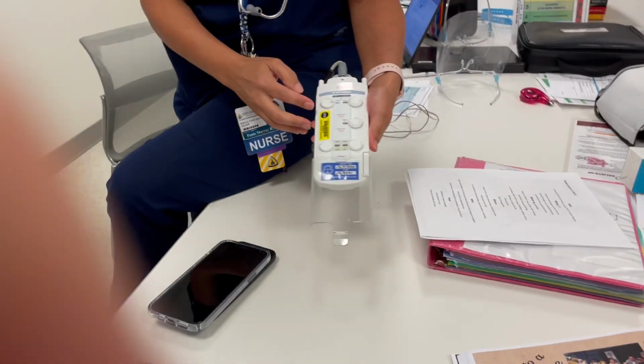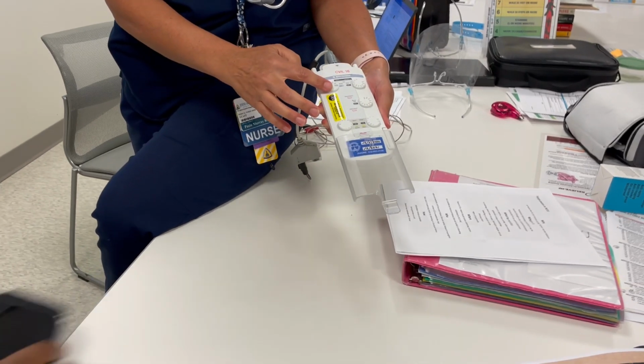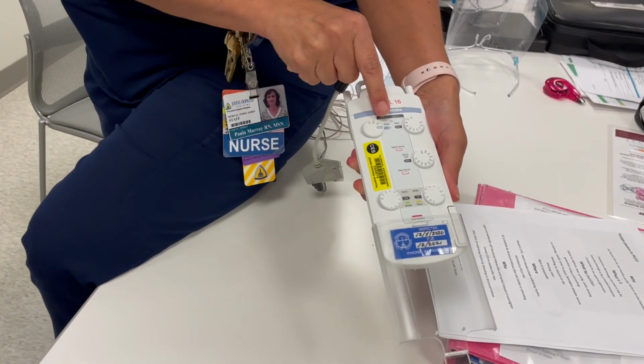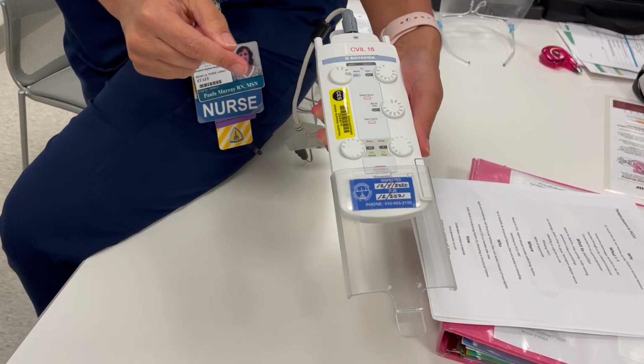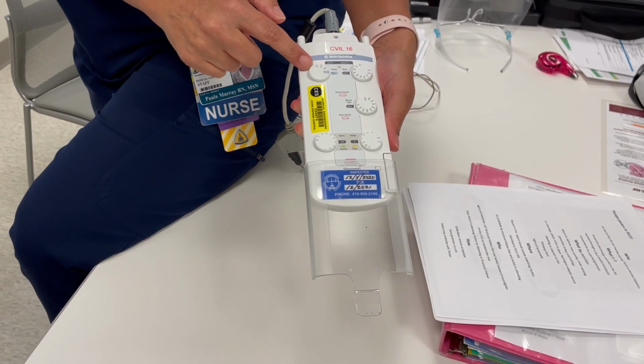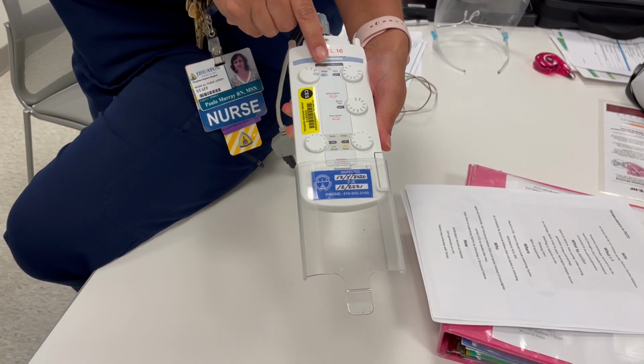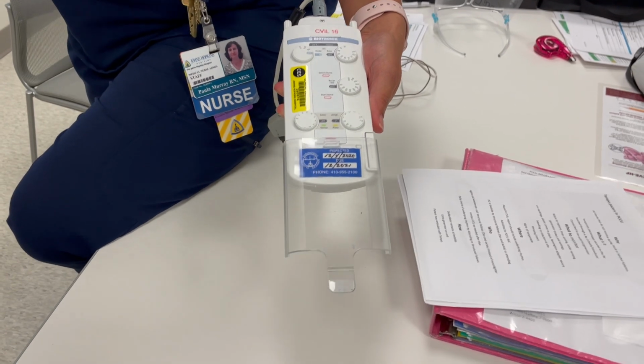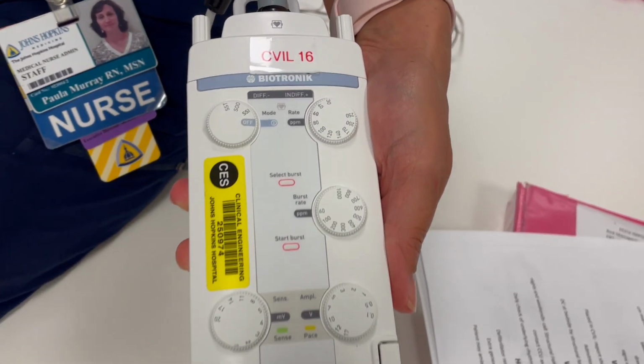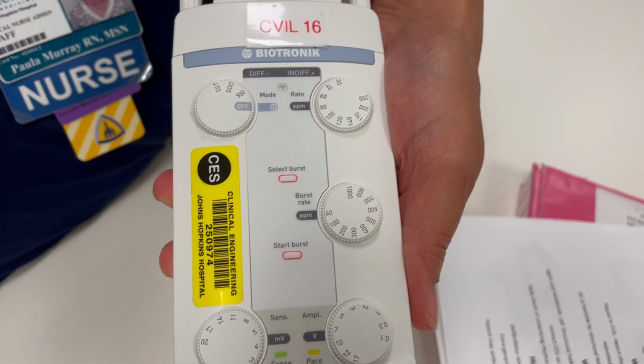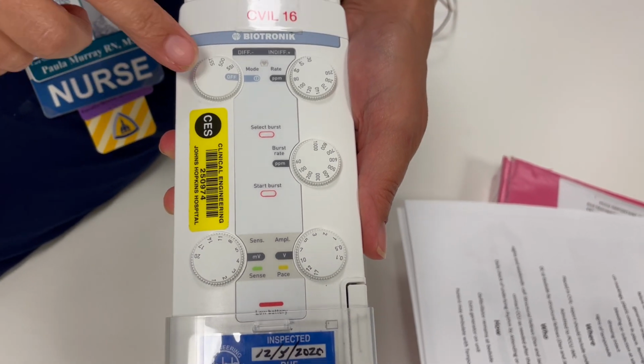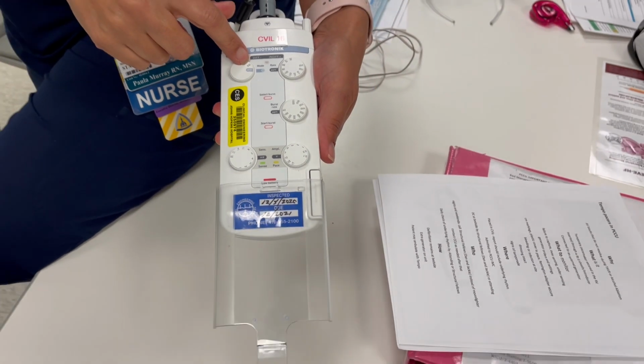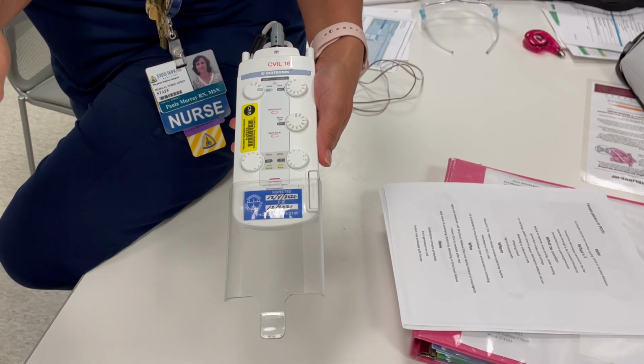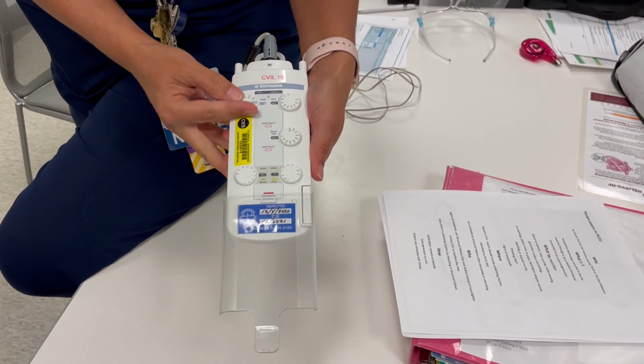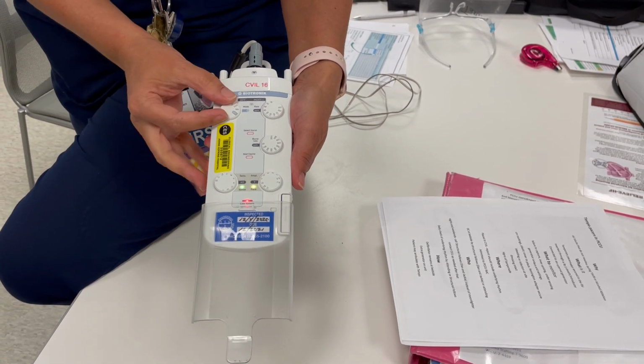So, going over the different buttons and dials: right here is the mode, and you can see it says mode. There are 3 different modes. The mode you are going to be using is the SSI, which is single chamber paced, single chamber sensed, and single chamber inhibited, okay? This is the same as VVI on the permanent pacemakers. So it's going to be on there.